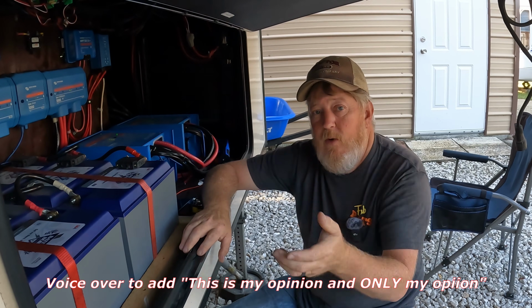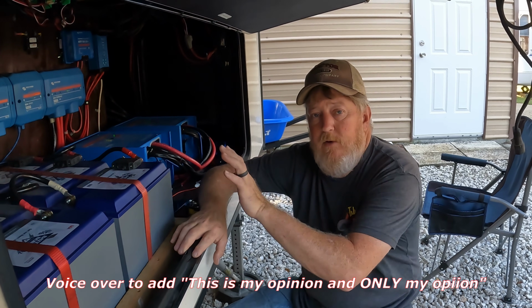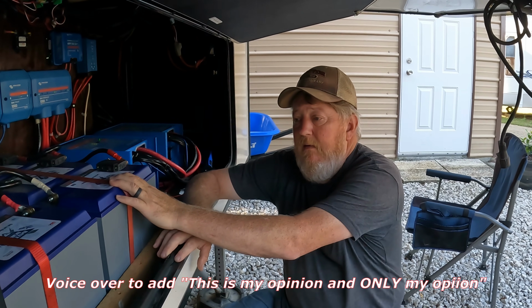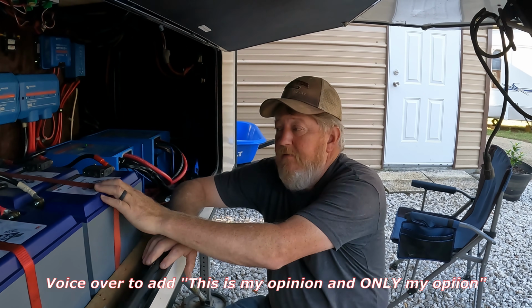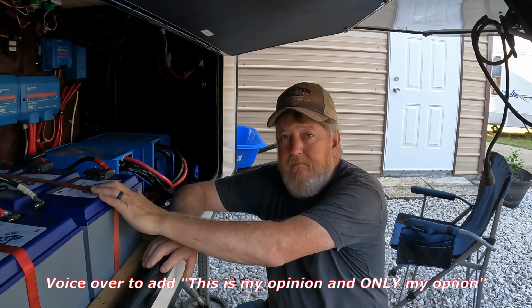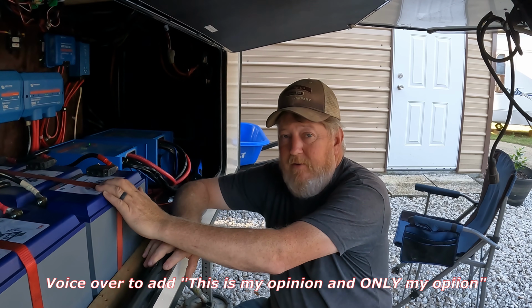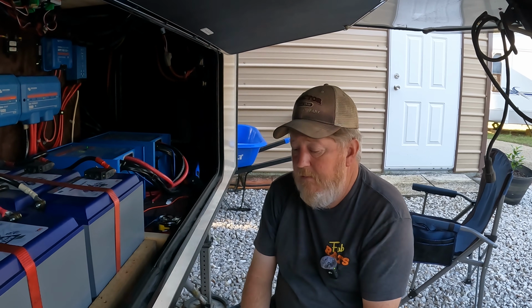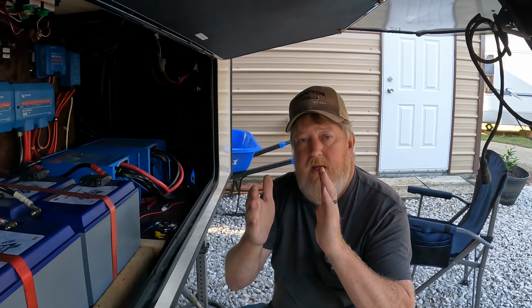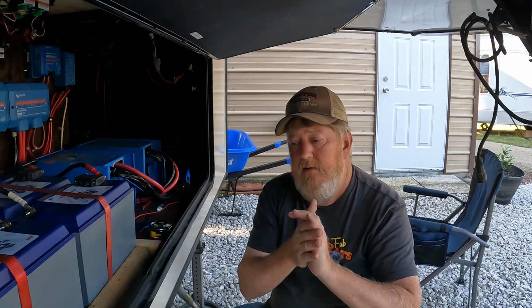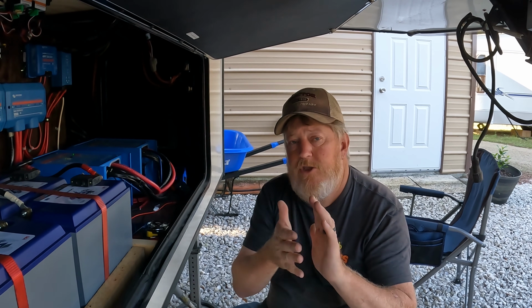If you've watched any of the Will Prowse videos, you've seen what I consider a design flaw in the way Battleborn manufactured this, with plastic in between the two connections. Again, this is my opinion, but as a lifelong electrician with 20 plus years in the solar industry, one thing I know is when you make a connection between a bus bar and a lug, you bolt them tight together and the bolt holds them together. The actual electrical connection is the lug to the bus bar. The bolt is just there to hold them tight. You never put something in the middle, like a washer. That just adds resistance.